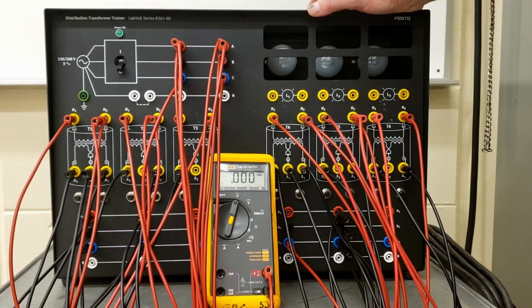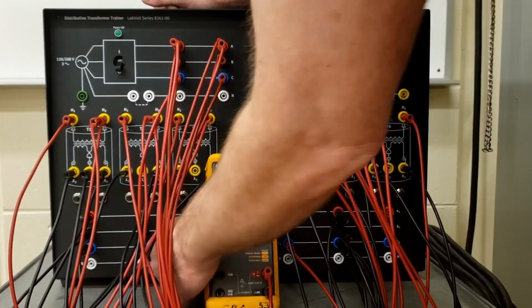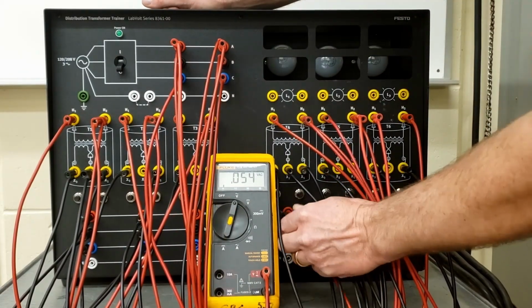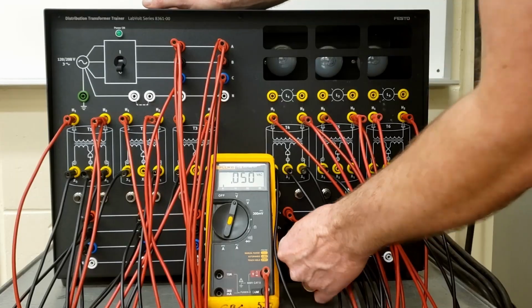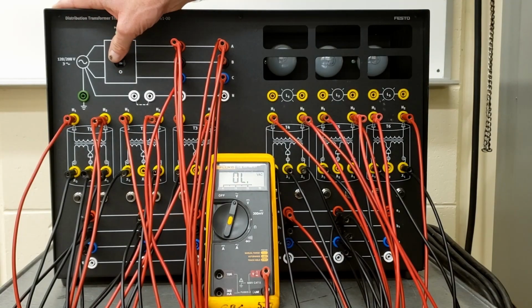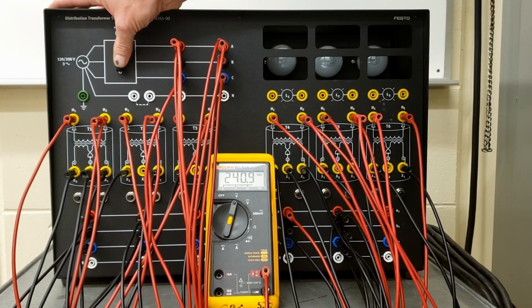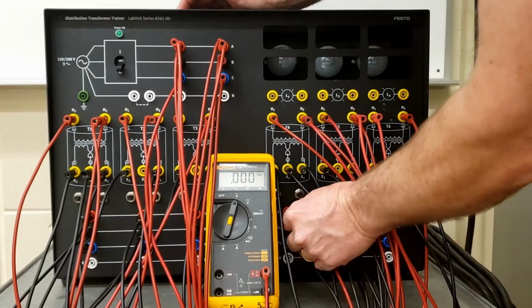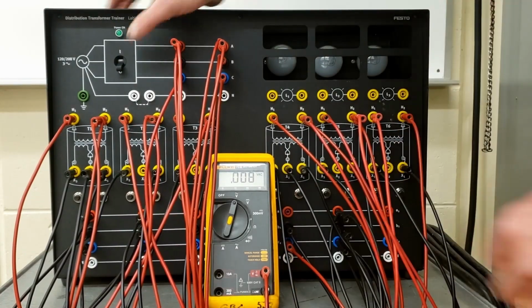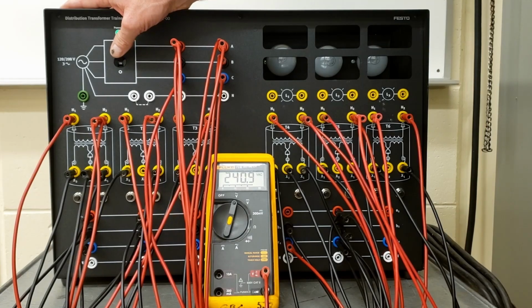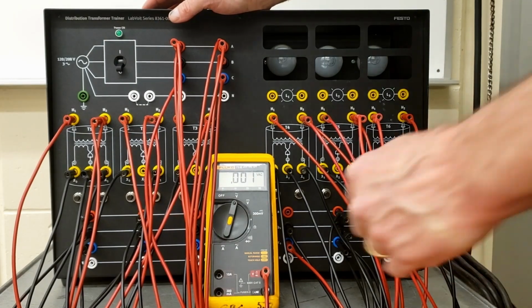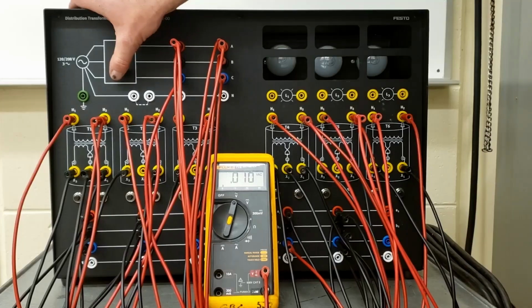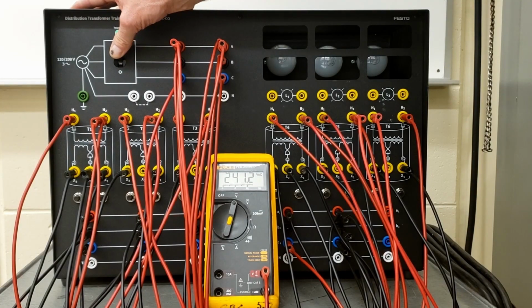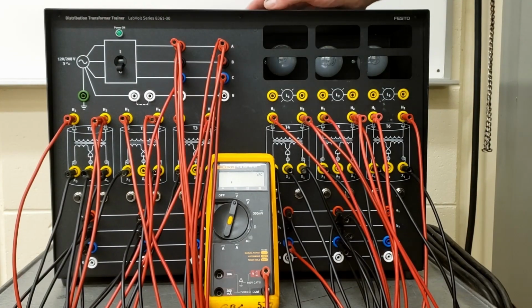It's actually asking us to look at the voltage between A2 and B2, so on the secondary side this should be 240 volts. Okay, that's good. Then it asks for the voltage between B2 and C2 - that should also be 240 volts. Then finally C2 and A2 - also 240 volts. Beautiful. Then it says below, determine the voltage between lines A1 and A2.